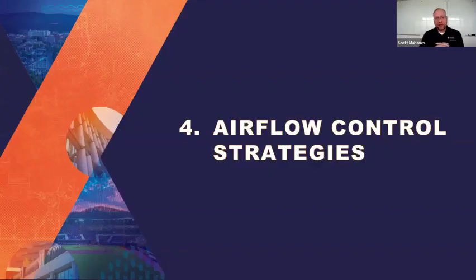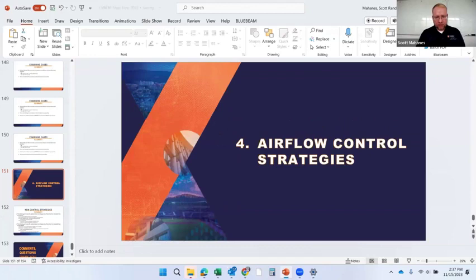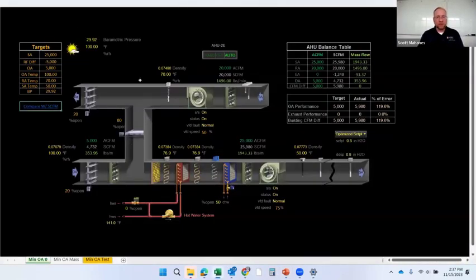Moving on quickly, let's see, how much time do I have? No time. Oh, I got some time. Okay. I want to go through simulation real quick on airflow control, because you can get the calibration on the flow sensors perfect, but the control of that airflow is still going to cause a little bit of a problem. And so for that, I'm going to go to this simulation.